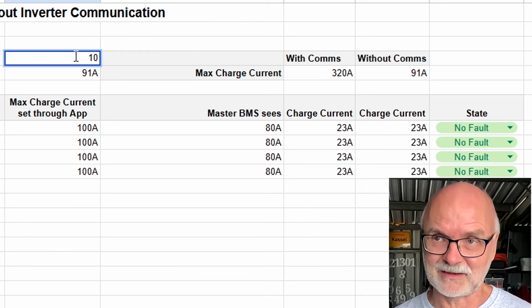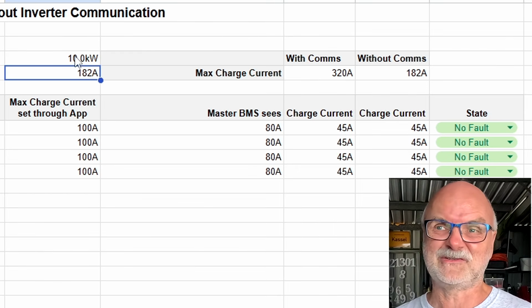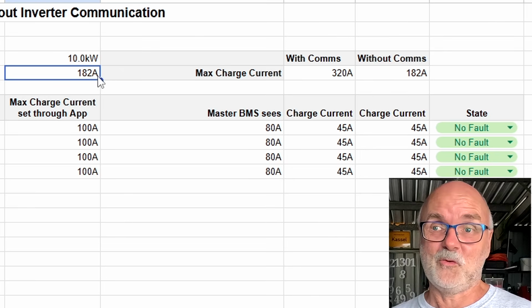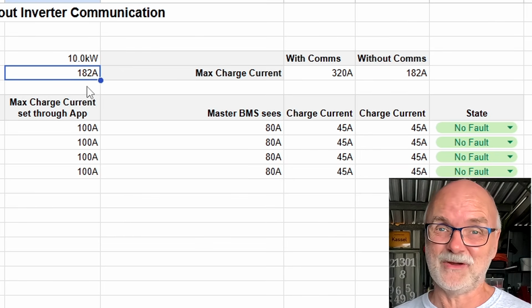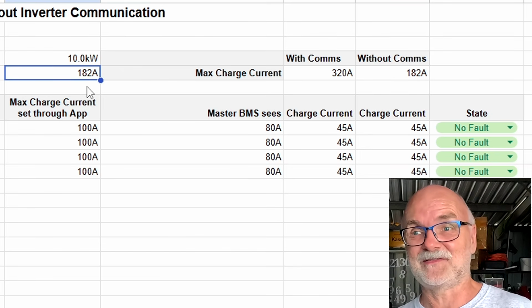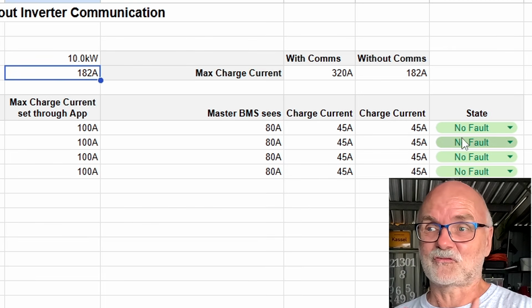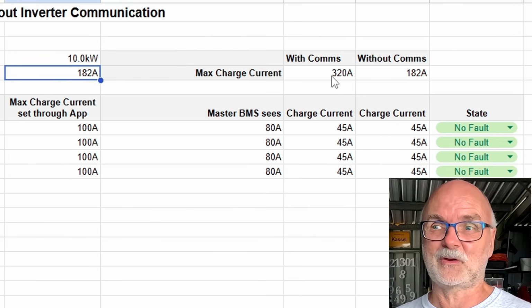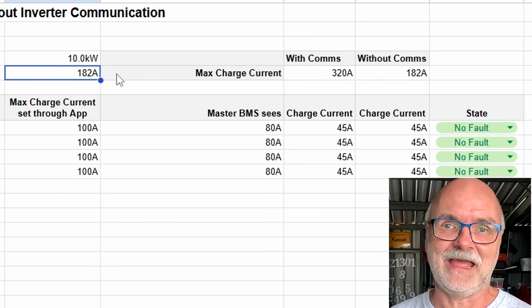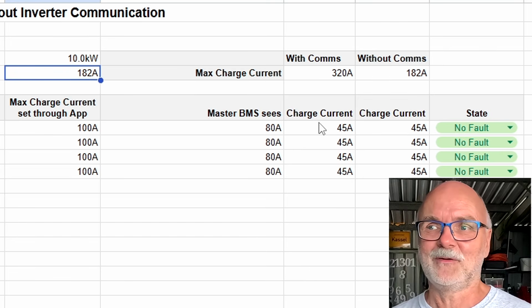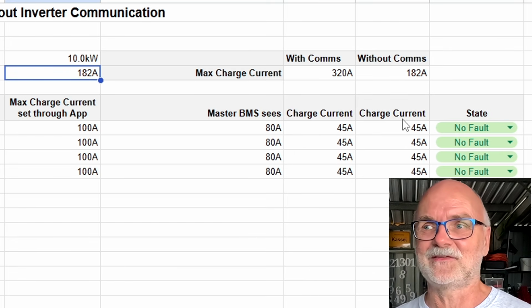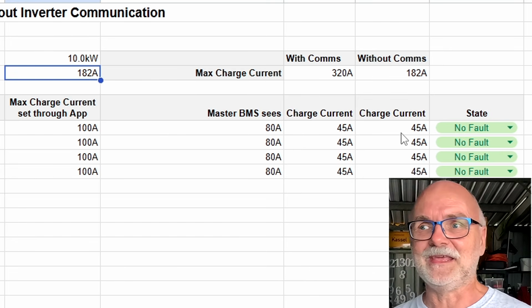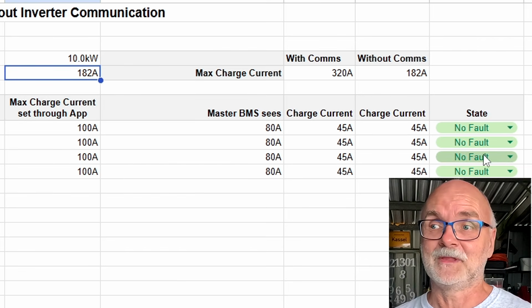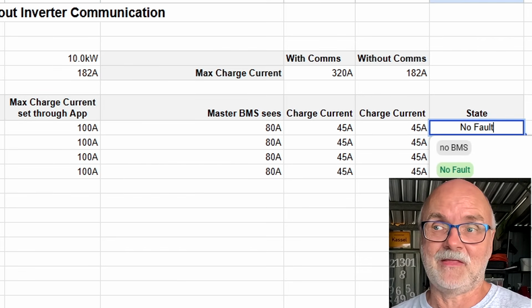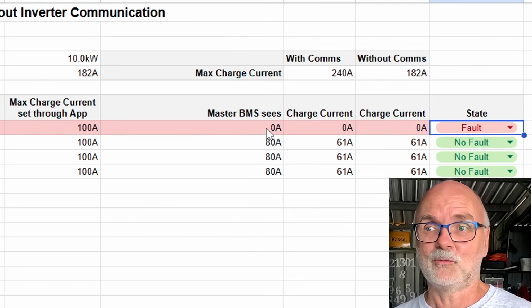So let's double this to 10 kilowatt. 10 kilowatt is not a big system these days anymore. So we are now having 182 amps coming from your solar system into these batteries. Yeah, everything is green, no issues at all. We are requesting 320. Your solar system can do only 182 amps. No problem. We're getting 45 amps into each of the batteries, the same as without the communication. Yeah. So let's do another fault here in one of the other batteries. Bang. Fault, one trips out.